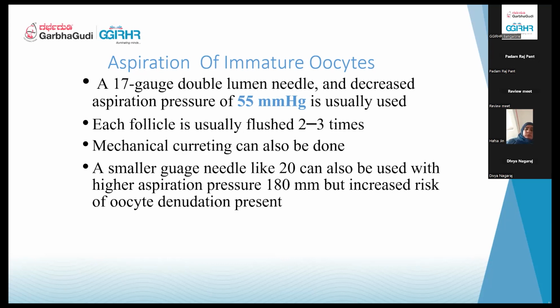You reduce the pressure. So why are you doing this? When you increase the size of the needle, then you need to reduce the pressure so that you maintain a constant flow rate. Then when you reduce the inner diameter of the needle, you increase the pressure again, so that a good, proper pressure is maintained for aspiration. For a 20 gauge, it is 180. For a 17 gauge, it is 55 for IVM.